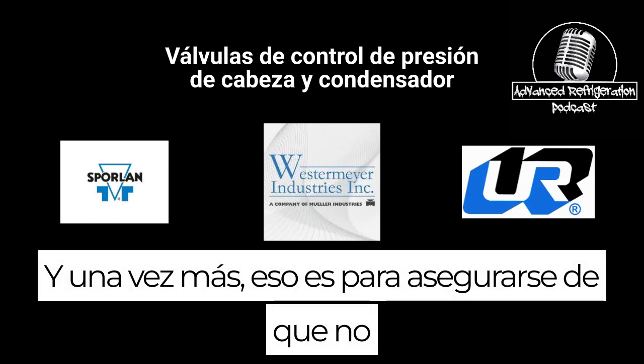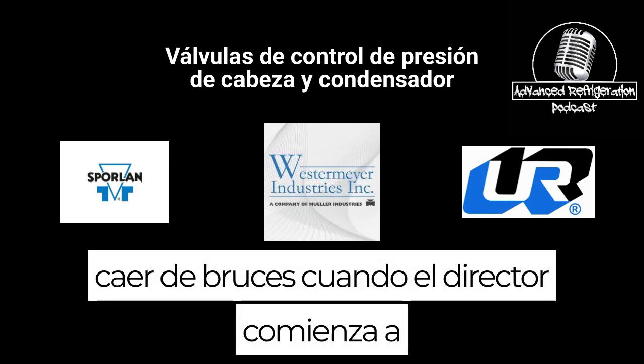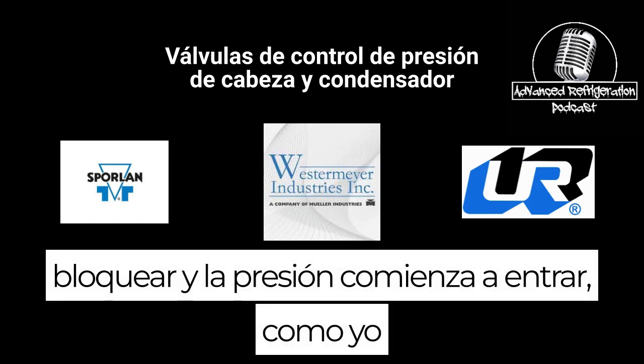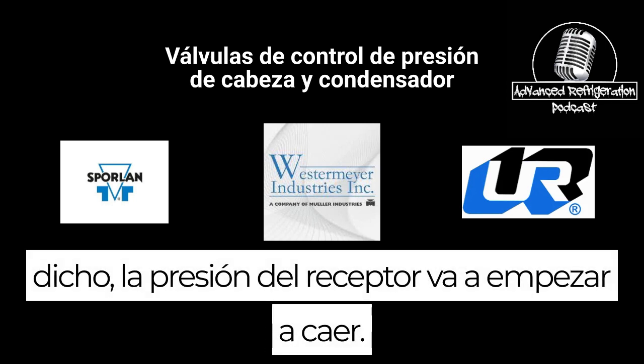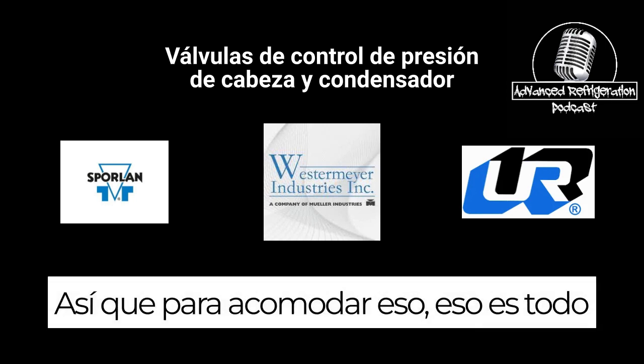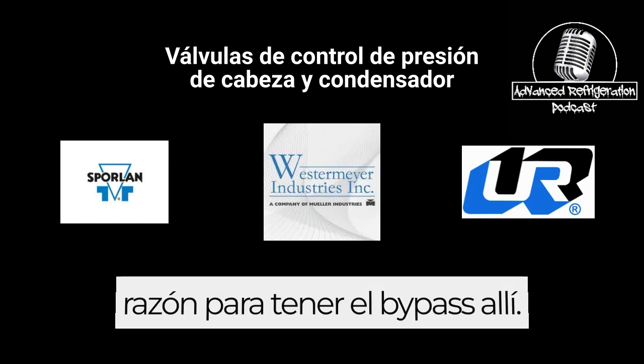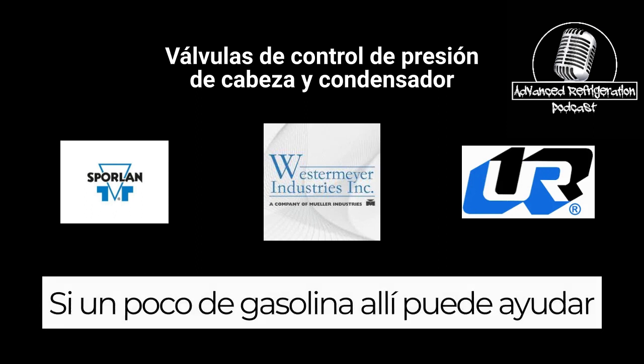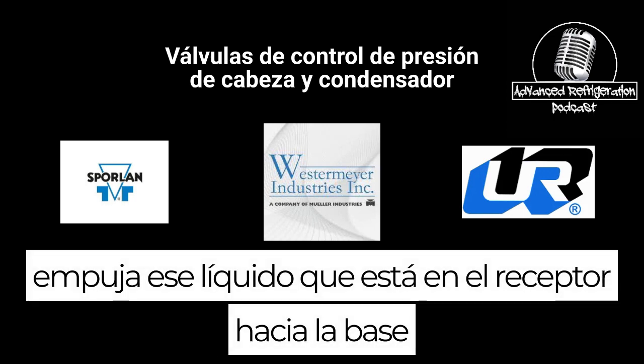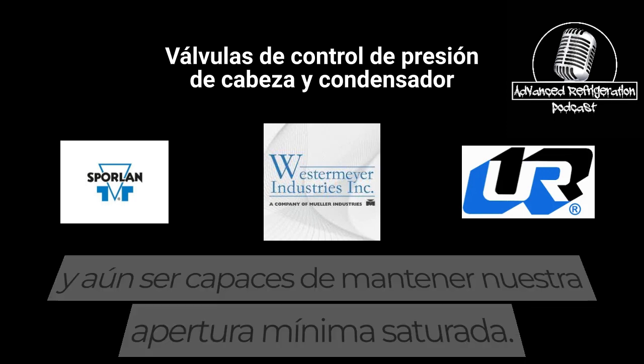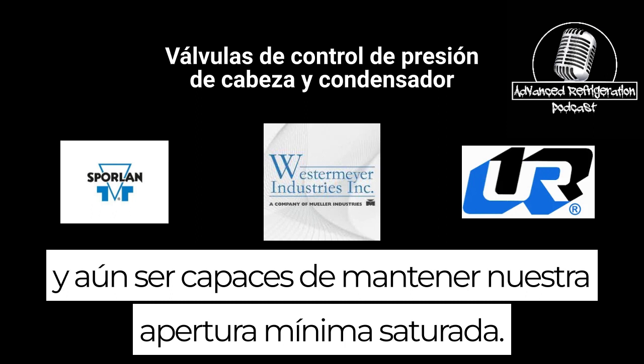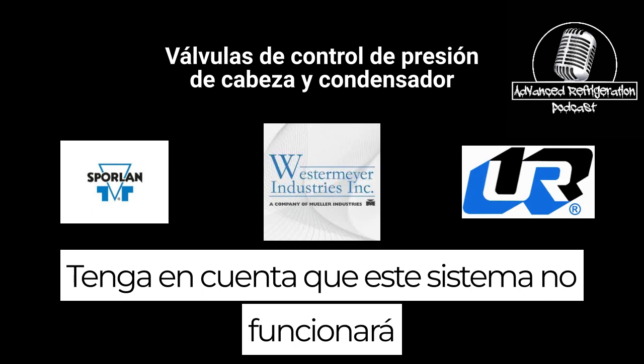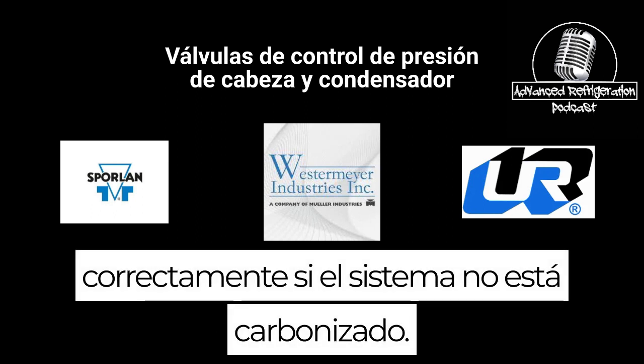Once again, that's to make sure that we don't fall flat on our face when the headmaster starts to block off and the pressure starts to rise in the condenser. Like I said, the receiver pressure is going to start to drop. To accommodate that, that's the whole reason for having the bypass on there. If you need a little bit of gas in there, it can help push the liquid that's in the receiver out to the cases and still maintain our minimum saturated condenser temperature. And be mindful, this system will not work properly if the system is not charged.